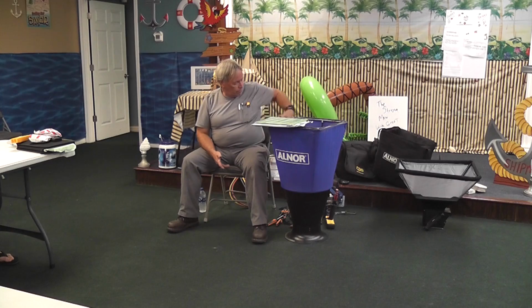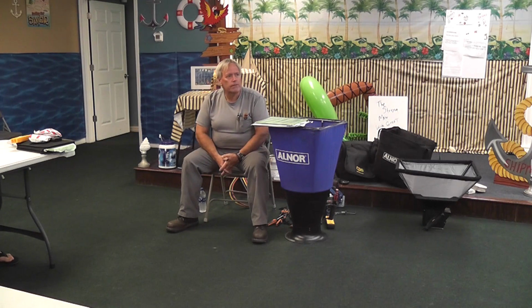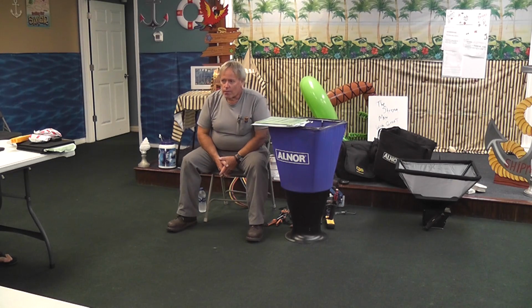Hence the stuff that's here. We'll see if we can check the system next door and find out how it's doing and what it's doing. Measure quick. You can input all the information that it needs, and it will tell you the efficiency, it will tell you all the psychrometrics of it, which psychrometrics are the temperature drops, the humidity removal. It gets into engineering. That will tell you what a system is doing, how it's doing.